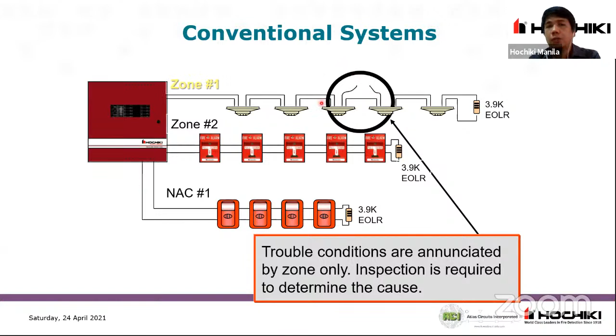Trouble conditions are annunciated by zone only. Inspection is required to determine the cause. So another is for the trouble. So pag nagkaroon tayo ng open circuit trouble dito, hindi nyo rin siya ma-pinpoint immediately kung nasaan. Kasi sa zone yan, so the whole zone yung wiring natin na yan yung i-check natin in case nagkaroon ng cut doon sa wiring. Okay? So kapag sa zone 1 yung nagkaroon ng open circuit trouble, hindi natin ma-identify immediately yung specific location. So kailangan natin hanapin all throughout doon sa zone 1.